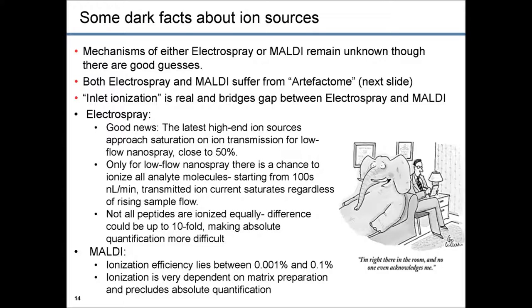For MALDI, we have different elephants in the room. First, ionization efficiency in MALDI is actually pretty low — it's between 10⁻⁵ and 10⁻³, meaning 99.9% of the sample is never seen in the mass spectrometer and gets lost. Also, ionization is extremely dependent on matrix preparation, and this precludes absolute quantification. Though for qualitative analysis it is great because of its speed.